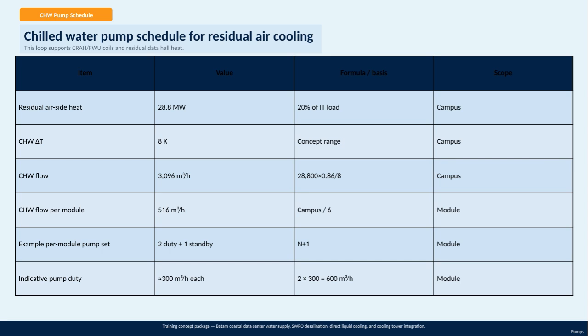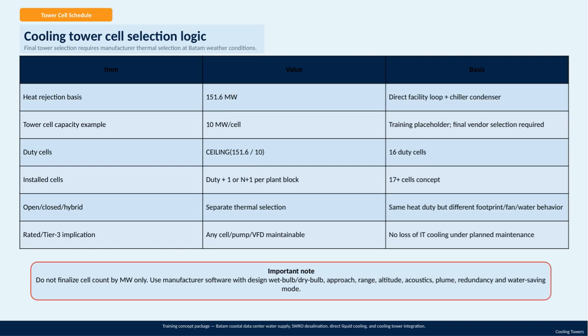For each module, the pump configuration follows an N+1 redundancy, meaning each set includes 2 pumps running in duty and 1 pump on standby. Each pump is expected to handle about 300 cubic meters per hour. So together, the 2 duty pumps provide around 600 cubic meters per hour for efficient and reliable operation. This setup ensures robust cooling performance and system reliability for the data center. Let's talk to the tower cell schedule and how we select cooling tower cells.